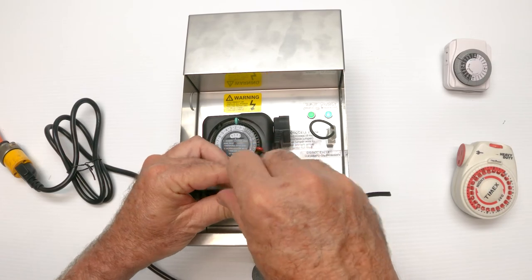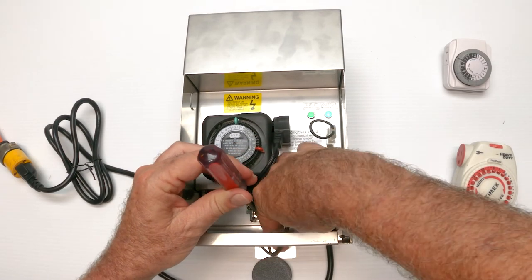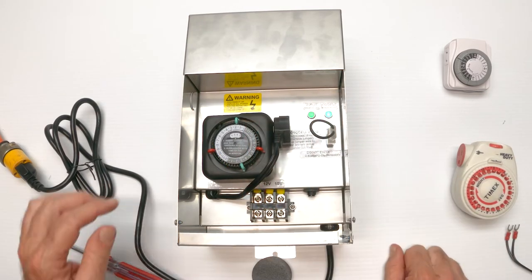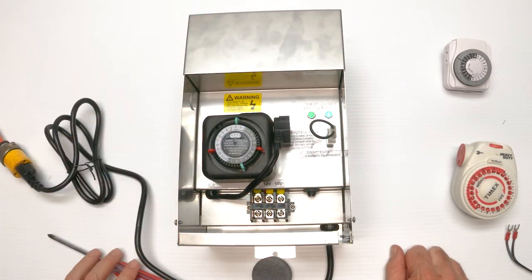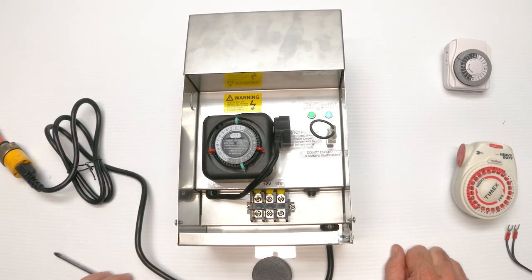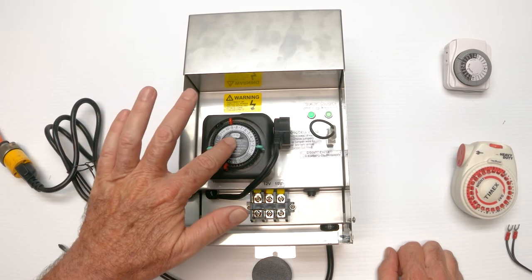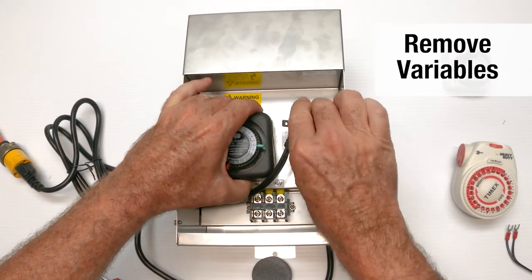You need to test your transformer. Loosen the screws. Please don't take them out. Take your load wires out. Here they are going out to the field. Then test your transformer. Make sure both lights are on. And you can kind of work backwards here too. Well, let's say the indicator light is not on. All right. The timer could be off or the timer could be defective.